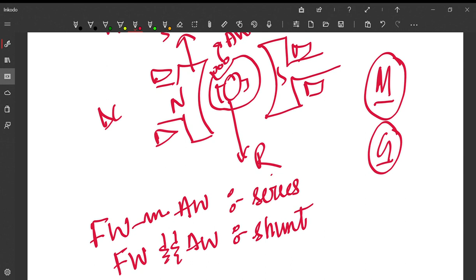in a DC machine, if the field winding is in series with the armature winding, we call this a DC series motor or DC series generator. If the field winding is parallel to the armature winding, then it is called a shunt motor or shunt generator. If the field winding has two parts, one in series with the armature winding and one in parallel with the armature winding, we have one armature winding and two field windings. Such a motor is called a compound motor. However, each and every motor will be explained specifically in the further lecture notes.